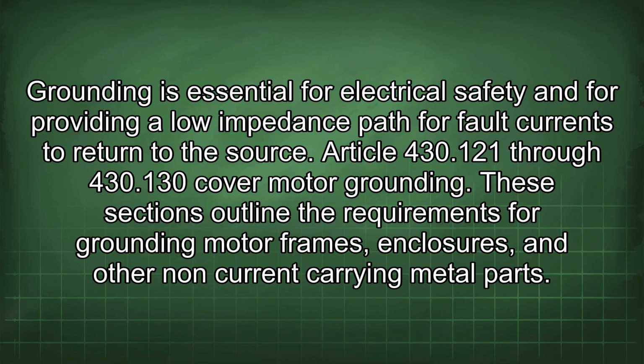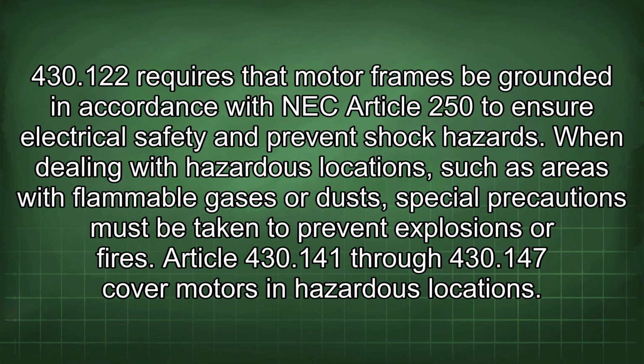Article 430.121 through 430.130 cover motor grounding. These sections outline the requirements for grounding motor frames, enclosures, and other non-current carrying metal parts. 430.122 requires that motor frames be grounded in accordance with NEC Article 250 to ensure electrical safety and prevent shock hazards. When dealing with hazardous locations, such as areas with flammable gases or dust, special precautions must be taken to prevent explosions or fires.